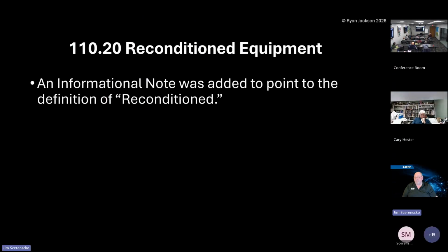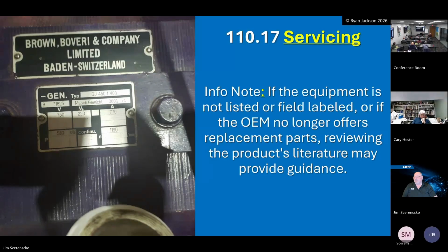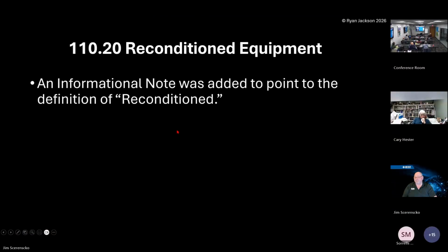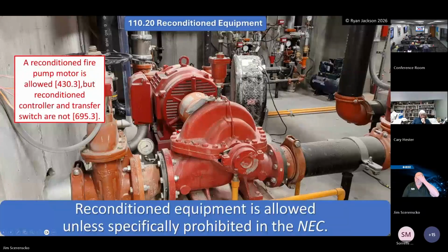That's an old piece of equipment right there. Brown, Boveri and Company Limited. Reconditioned equipment. The controller and the transfer switch are not allowed to be reconditioned. The motor can be, and it doesn't have to be listed either. Motors never have to be listed because really all they're doing is changing the windings.